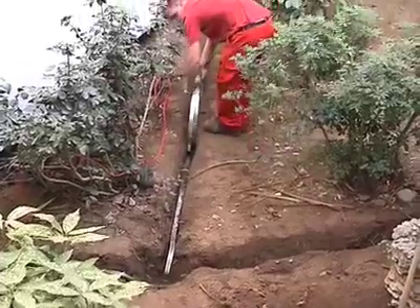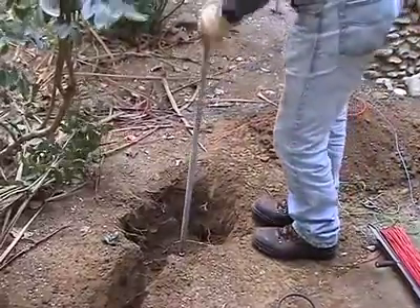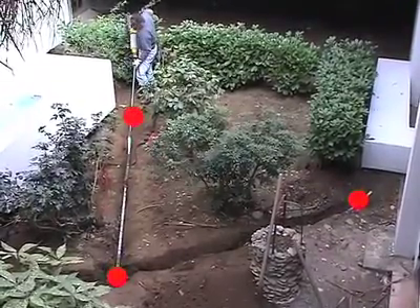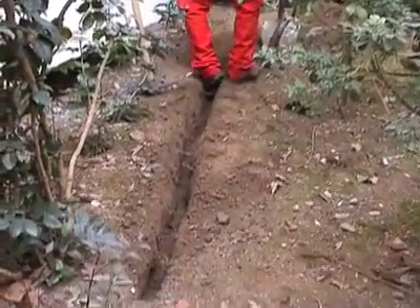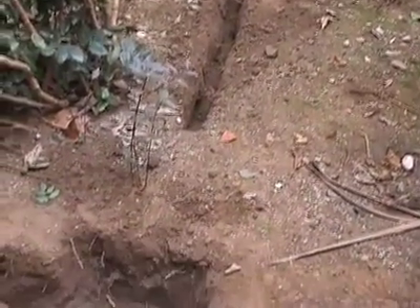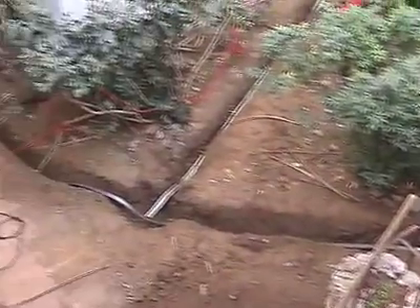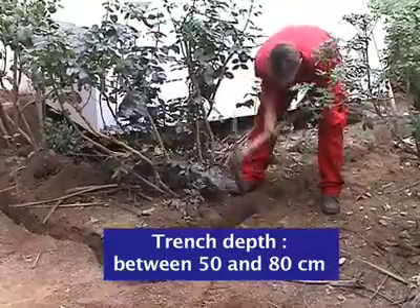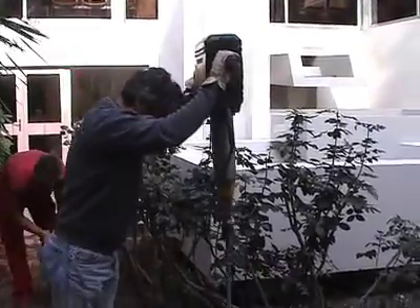With regards to the small space allowed in this particular site, you will notice that the earthing system has a triangular shape. This earthing system will be made of tin-plated copper tape and three earth rods. The trench should be as narrow as possible in order not to change the initial structure of the ground too much. Its depth should be at least 50 centimeters to keep it away from frost, but not too deep as the lightning current dissipates better in the ground surface.